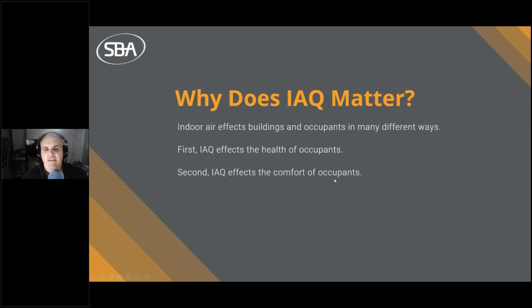From there, and this is where some folks will disagree, I say that we should focus on the comfort of the occupants. We've got a lot going against us trying to get people to reoccupy buildings. The last thing we want to do is create an uncomfortable environment, because if you could be like me right now, sitting in my basement where I have the AC set at 67 degrees because I like it really ice cold, and then I'm forced to go into a building that's implementing some sequence that is making it 75 degrees and 60% relative humidity, I'm going to be uncomfortable. I'm not going to like that. And if I don't have to go into that building, I'm not going to go into it. So we want to look at the comfort of our occupants in everything we do.